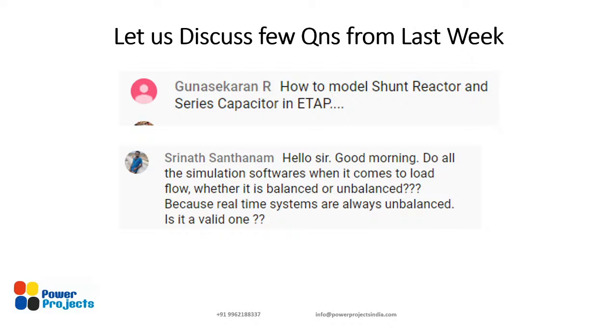But if you go with an unbalanced load flow, the time consumption, the modeling, the memory, everything goes up. If you are able to spend that much time, money and effort, then you can definitely go with the unbalanced load flow. But sometimes the unbalance in 400 kV or 220 kV systems is quite small, so you can very well assume the unbalanced system is a balanced system, and we do a balanced load flow. But it is always recommended to go for an unbalanced load flow, which gives more accurate results, close to practical systems, than assuming the unbalanced system to be balanced.